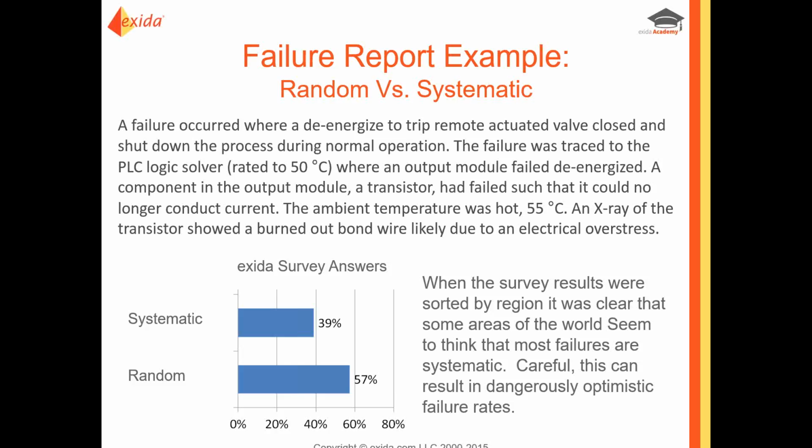And in this particular example, where we had a real failure that caused a real shutdown, 39% of the people surveyed called it systematic. Now, why is that important? In many data analysis systems, systematic failures are thrown away. Yeah, you heard me. They take the failure reports and throw them away. They don't count them. Even if they're real.